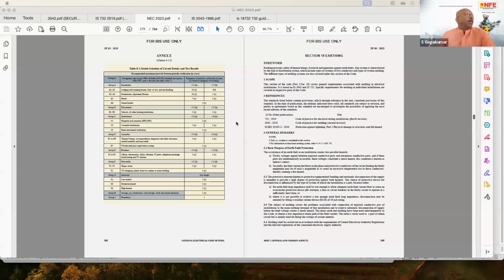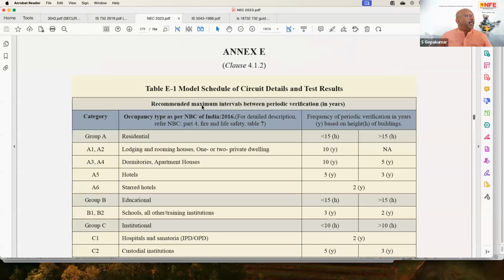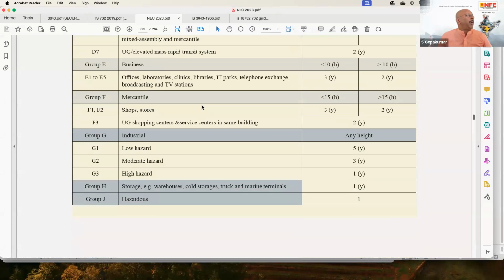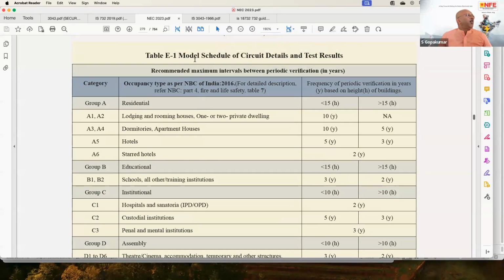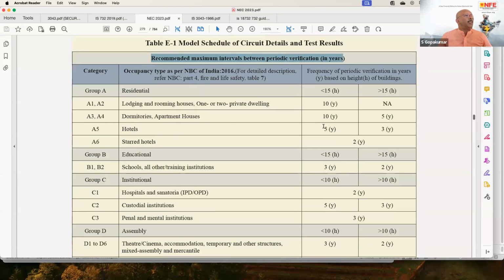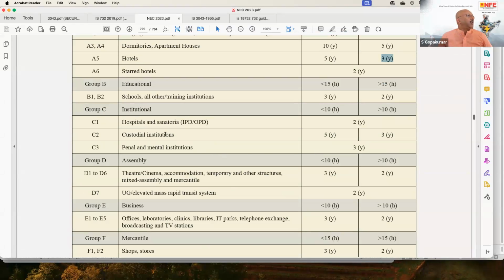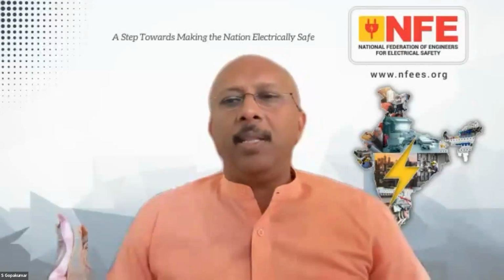Yes, I will just show that particular annex so the participants can see. So this is the annex which I am referring to. Page number 268. Model schedule, recommended maximum interval between periodic verification in years. For example, hotels, 5 years. If the height is less than 15 meters, 5 years; more than 15 meters, 3 years. So you can find different periods mentioned in the standard.